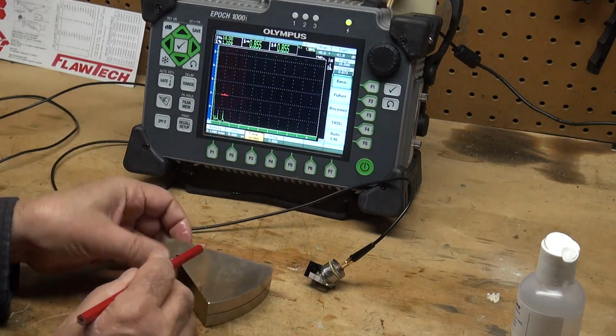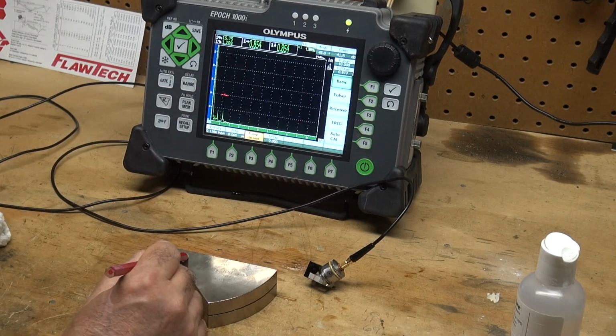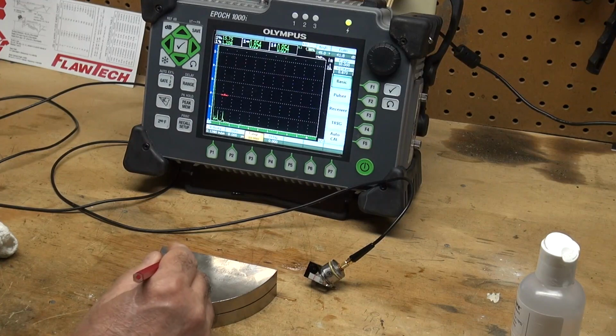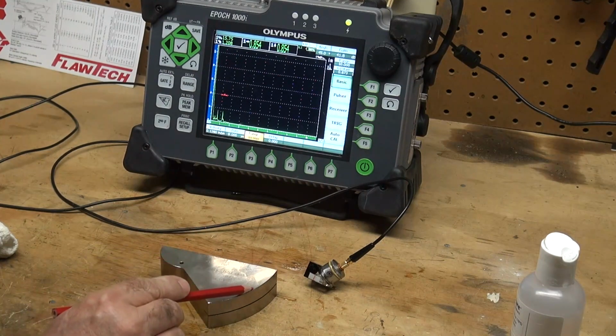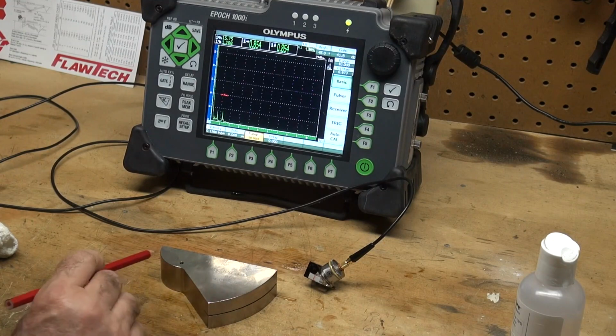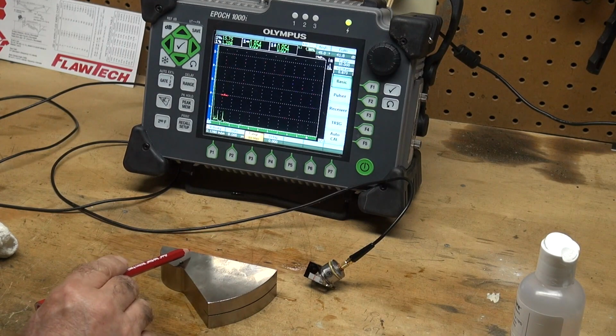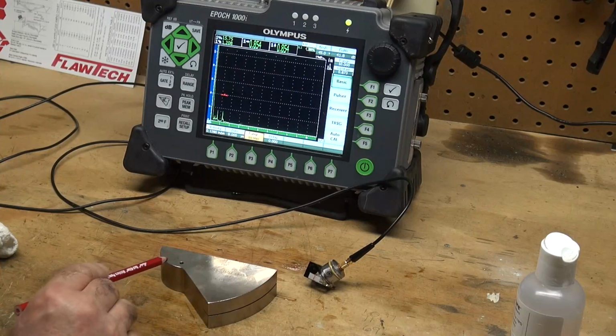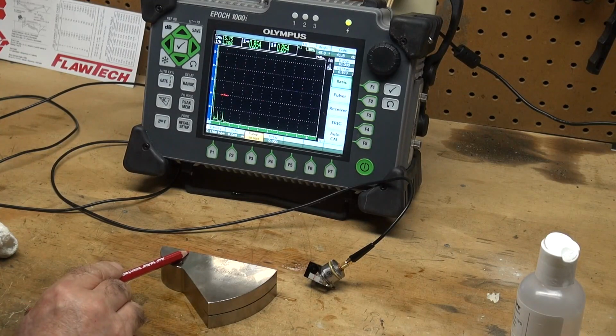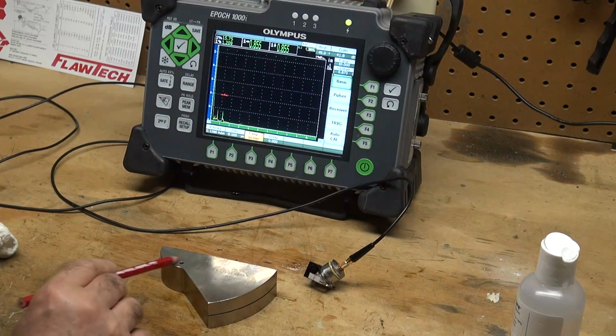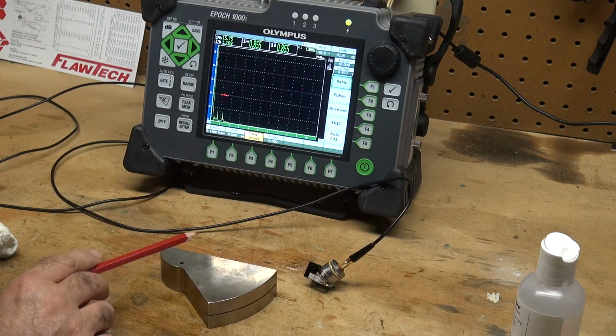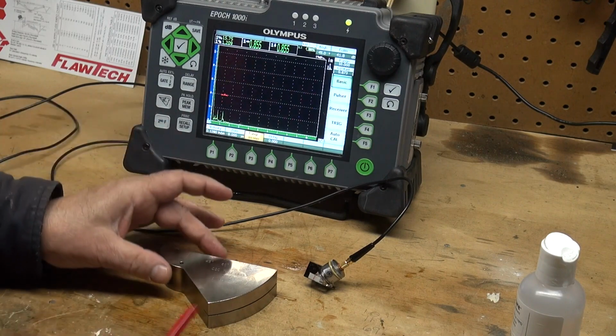This block has the 0 for your beam index point machined right here. And then the radius, from the 0 to here, this is a 1-inch radius. And then from here to here is a 3-inch radius. So when I put my transducer on here, I will see a 1-inch reflector, plus 3 is 4, plus 1 is 5, and then 4 more would be 9. So I'll see a 1-inch, a 5-inch, and a 9-inch reflector.